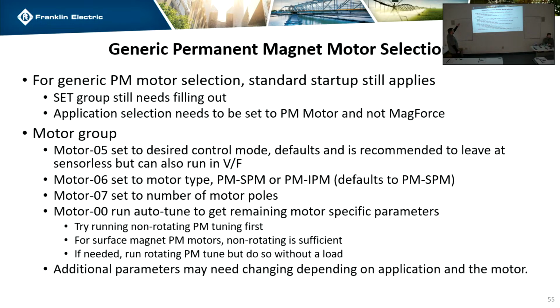You set the set group up just like everything else. The application select will have to go to permanent magnet. And then you go to the motor group, and it's just like doing a motor setup. Like I said, it's just more details. It's going to ask you the number of poles, the type of motor. If you want to do an auto tune, the drive can set it up with an auto tune. But you have to do this without a load. So the motor has to be there without a load on it. If it's just not realistic to get the load disconnected, you can do a manual setup. And then that's it. Yep, go to the next one.